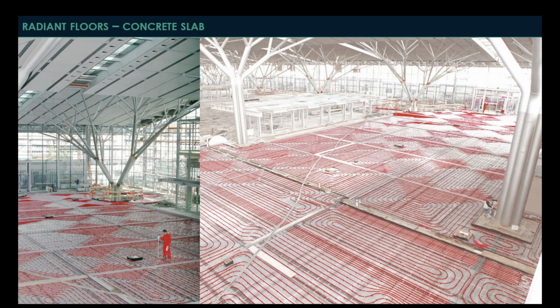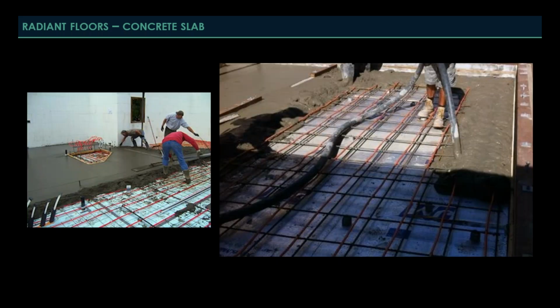So here you see an image of a very large, very open space that is utilizing a concrete slab. Now, this is the system before it has been poured, and I really like these images because it shows a lot of how these systems are installed, how they're laid out, and how they're zoned. You can see by the geometric patterns on the ground that each one of these areas is a separate circuit, right? So each of these circuits then get routed back to what we call a radiant manifold. We'll talk a little bit more about that in a second, but the takeaway from this image is that you can really cover extremely large surface areas with radiant floor systems, and oftentimes it's required to cover a very large area in order to get the capacity you need to heat and cool the space.